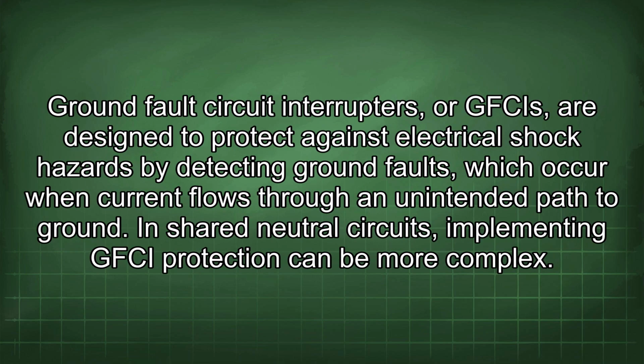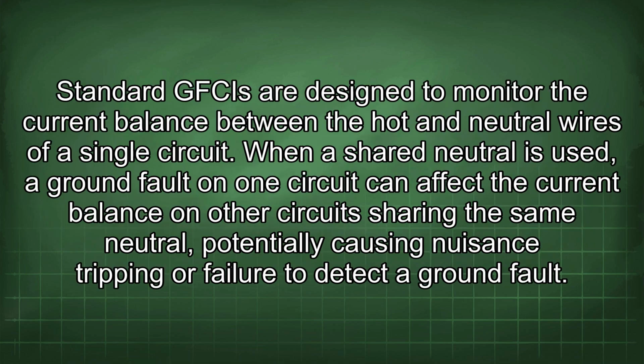Ground fault circuit interrupters, or GFCIs, are designed to protect against electrical shock hazards by detecting ground faults, which occur when current flows through an unintended path to ground. In shared neutral circuits, implementing GFCI protection can be more complex. Standard GFCIs are designed to monitor the current balance between the hot and neutral wires of a single circuit. When a shared neutral is used, a ground fault on one circuit can affect the current balance on other circuits sharing the same neutral, potentially causing nuisance tripping or failure to detect a ground fault.